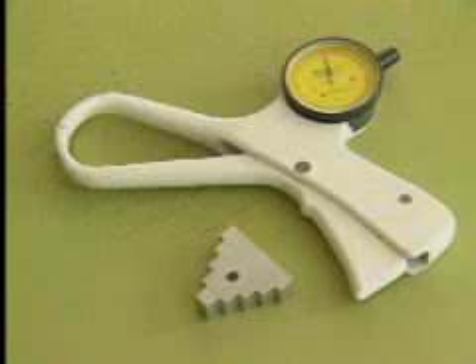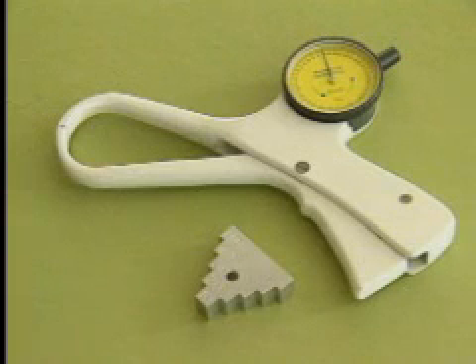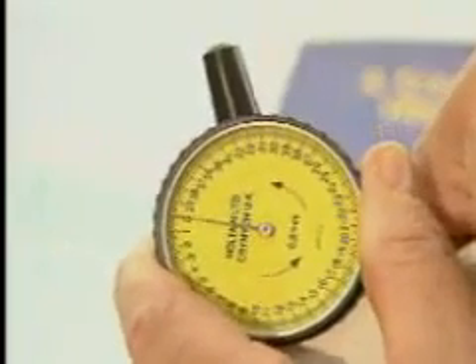The Holtain calipers have an adjustable dial that can be moved around to reset it if the needle has moved off the 0 mark. The fact that this can be done easily means that it will often move and should therefore be checked before every use. It is rare but not impossible for the calipers to go out of calibration.